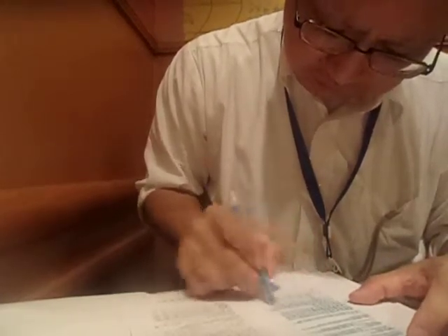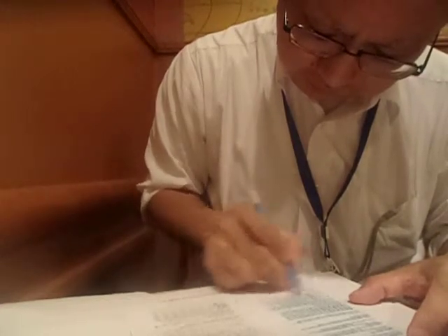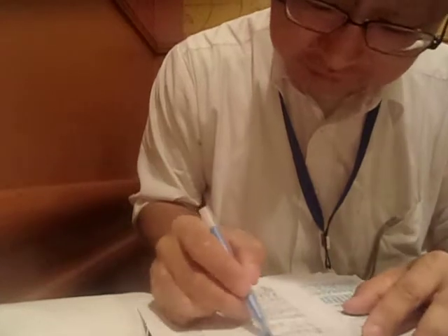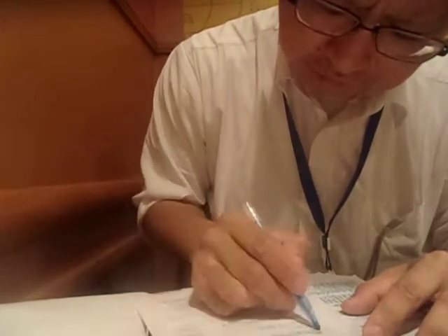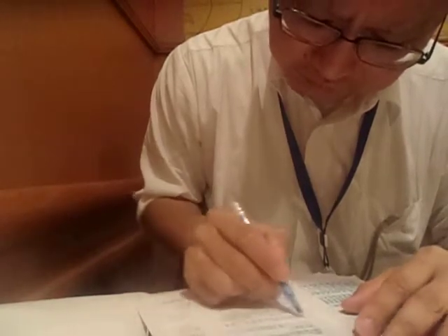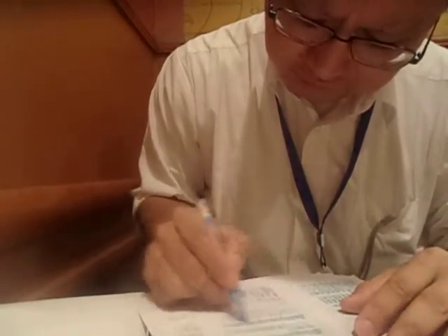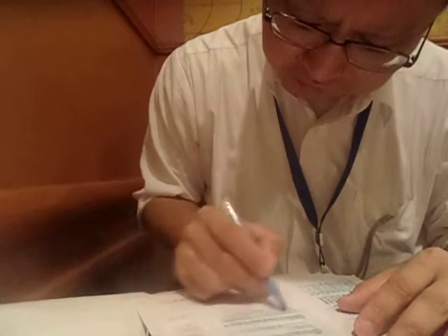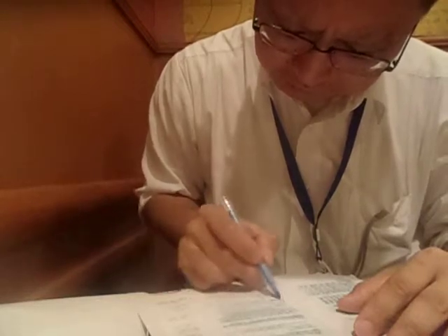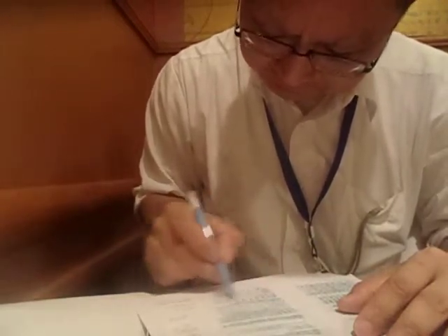These simple multimeters can't be used for this testing. So you need an AC true RMS meter to be able to do this testing, because it is not a clean sine that you're testing for. If you have a very weak signal, it is definitely no sine, and therefore this is very crucial to be able to do these tests.